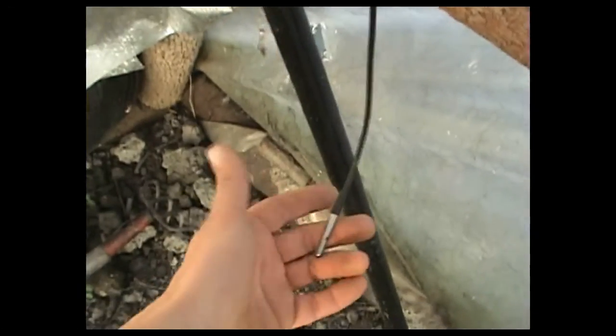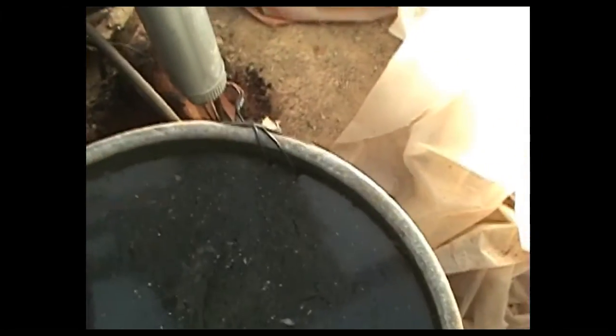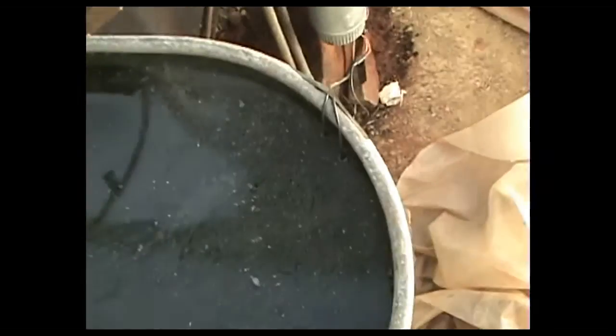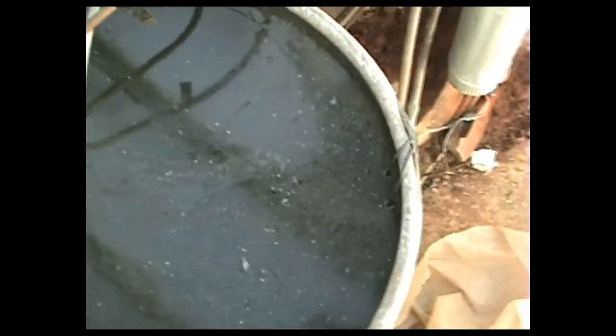One up here, one down here, so on and so forth. Also, in the two thermal mass tanks, there are two sensors each, a high sensor and a low sensor. So we get the high temperature and low temperature. We average the two of those, and then we calculate for BTUs based on the number of gallons of water in the tank and the number of degrees change.